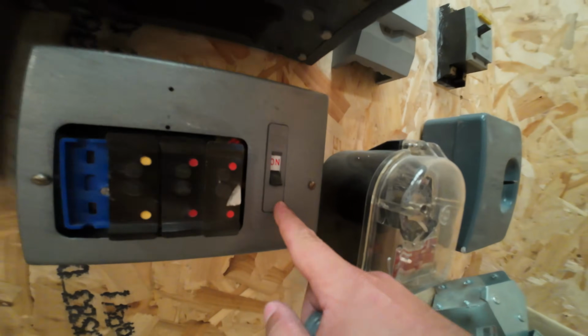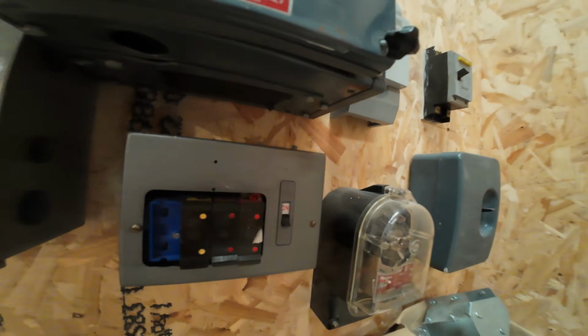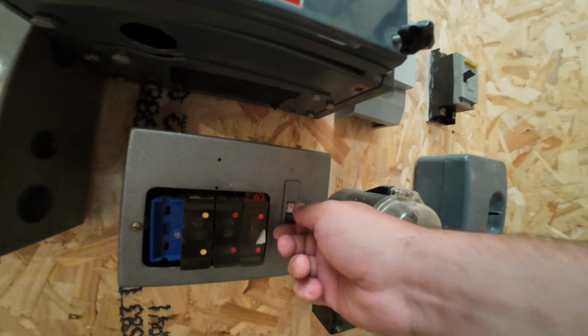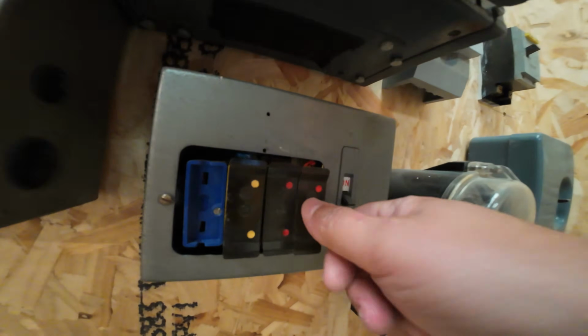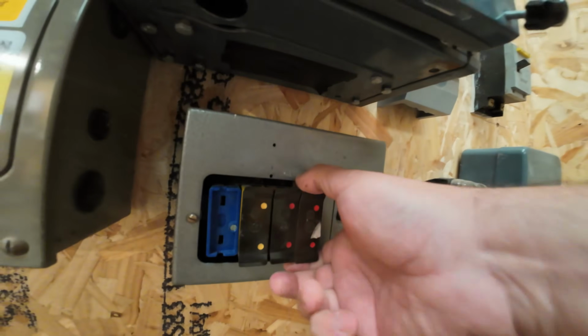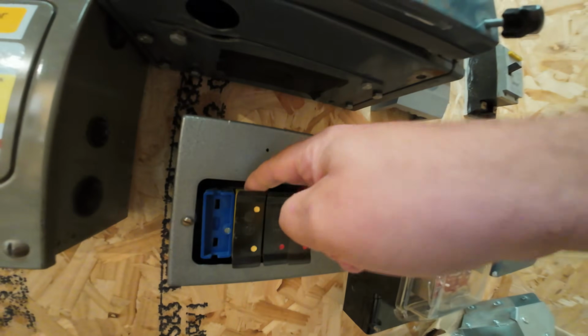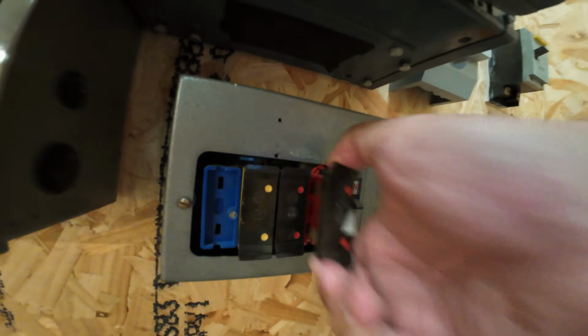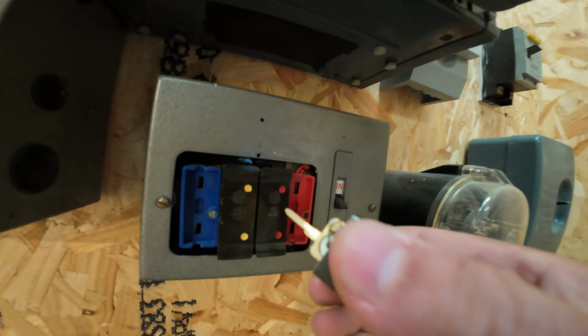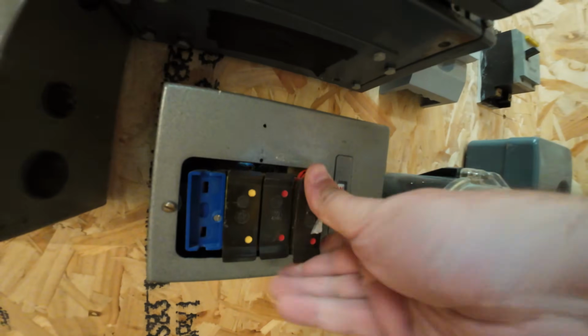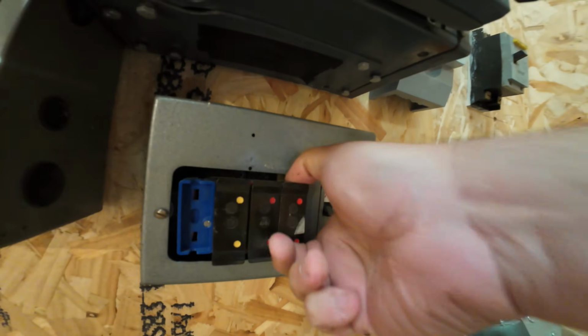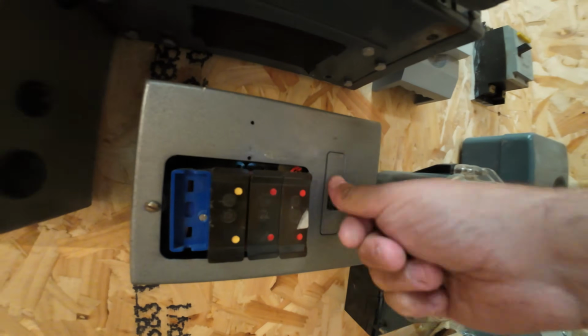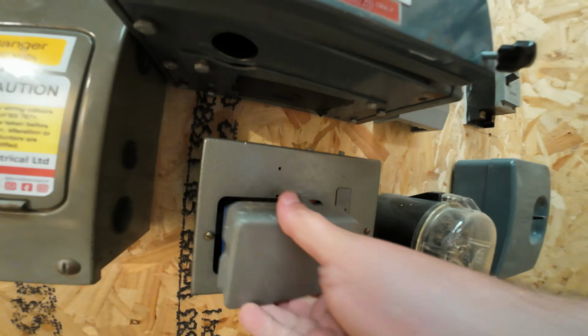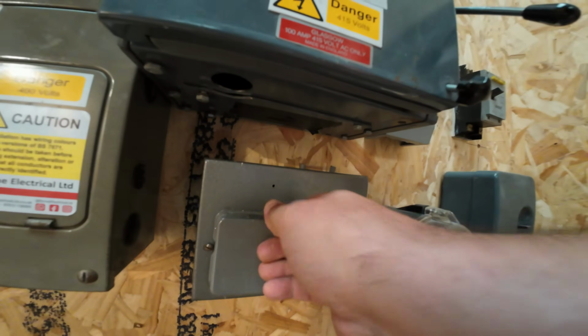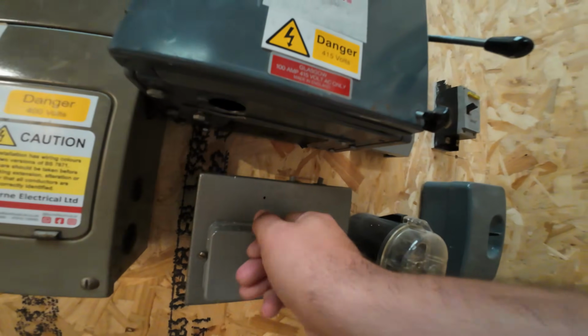The point to remember with these is when you are turning the power off with them, you should always do that before you start changing any fuses. If you're a trainee, don't simply pull these out, because the terminals here can be live. What happens is when DIYers change fuses, they're maybe not as accurate as we are, and those little threads in the bottom that you can see there could stick up, and you could stick your thumb or finger onto it and give yourself a nice belt. So always make sure you turn the isolation switch off if you come across one of these out in the wild and you're changing a fuse wire.